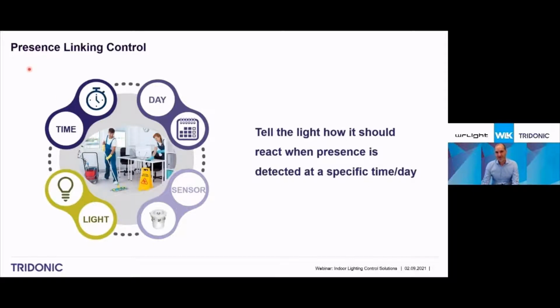Already in the simplest presence linking mode, or exceptions calendar, when it's a school or an office building, you can put the holiday calendar in the system, and then say there, even when presence is detected, all luminaires should go to full brightness, or every second one, or work with special scenes. That's already possible in the integrated presence linking mode, or presence linking app, as we call it in the system.